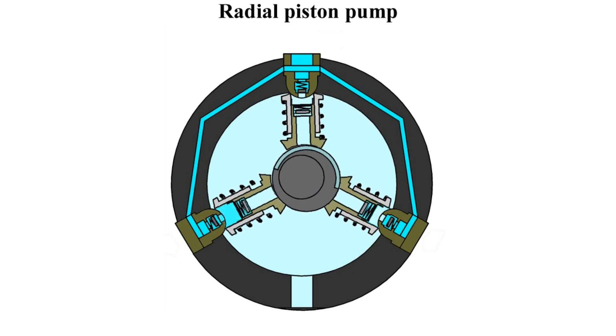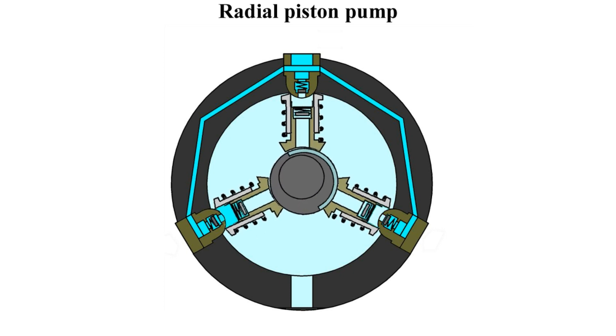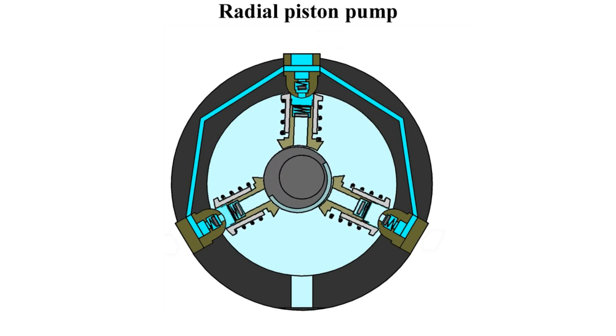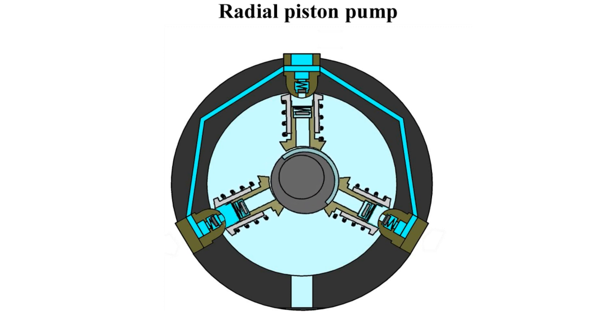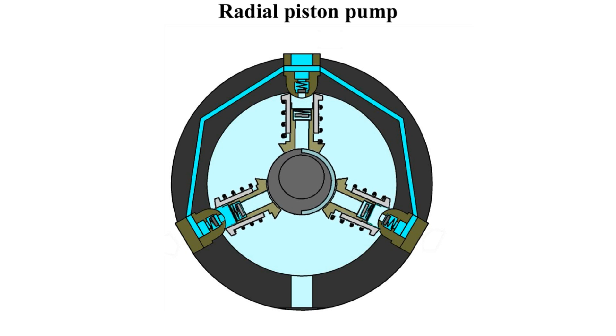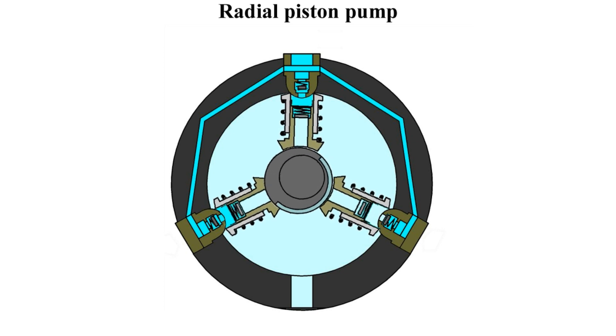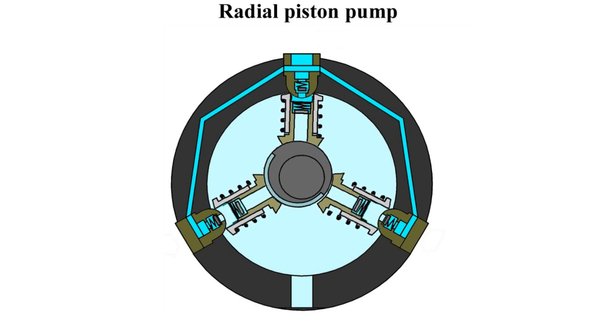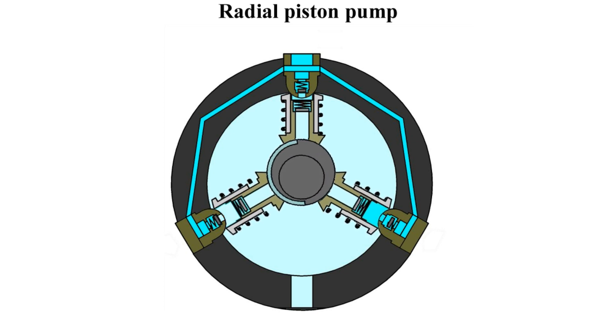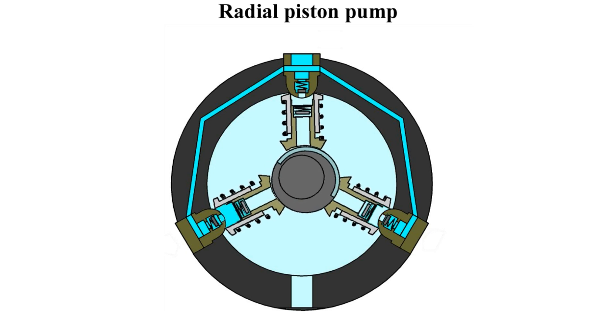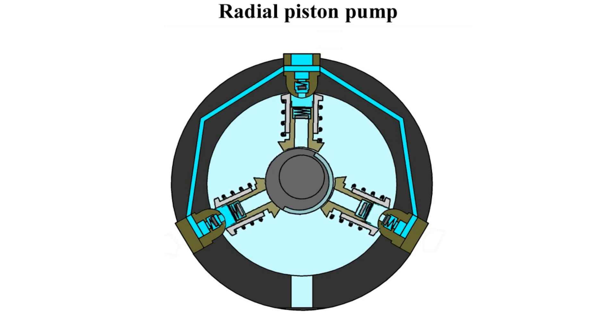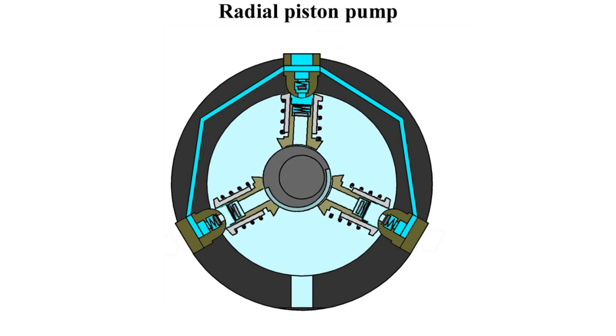When the piston is at the lower idle point, the suction valve and pressure valve are closed. As the eccentric rotates, the piston is moved in the direction of the pivot. Fluid is compressed in the chamber. Due to the pressure produced, the pressure control valve in the pivot opens and fluid flows into the high pressure line.